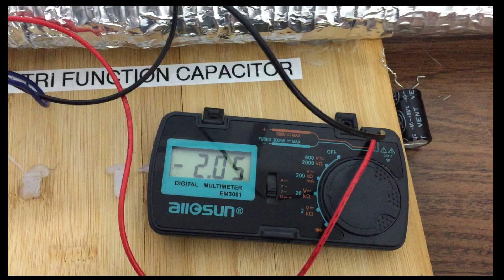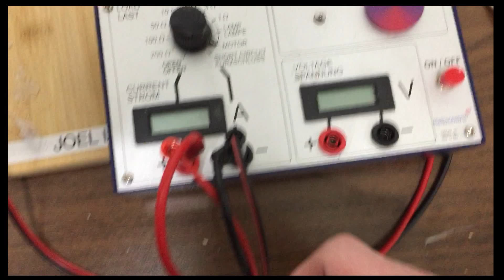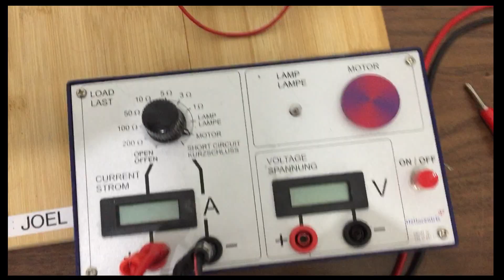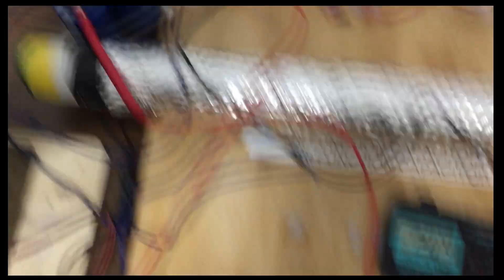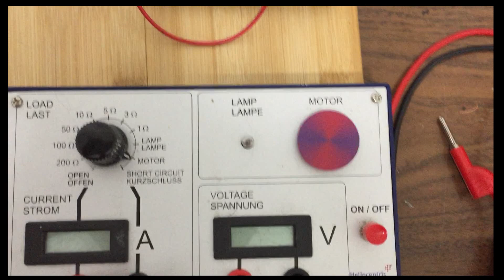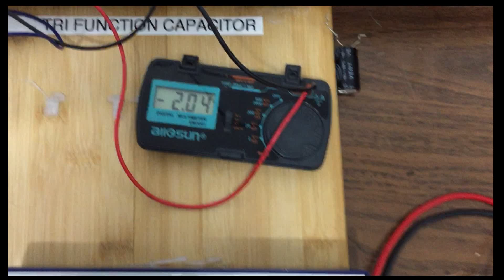So here I have it now measuring at 2.04, continuously rising. These two wires are connected to here, so I can short it completely. What you would expect is for it to go right to 0 after the initial discharge, right? And I've got the motor in parallel with this output, so the motor should stop right away and the voltage should go to 0, the path of least resistance, right?